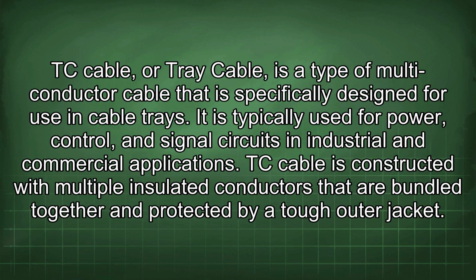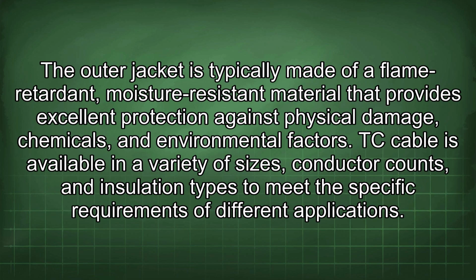TC cable, or tray cable, is a type of multi-conductor cable that is specifically designed for use in cable trays. It is typically used for power, control, and signal circuits in industrial and commercial applications. TC cable is constructed with multiple insulated conductors that are bundled together and protected by a tough outer jacket. The outer jacket is typically made of a flame retardant, moisture-resistant material that provides excellent protection against physical damage, chemicals, and environmental factors.